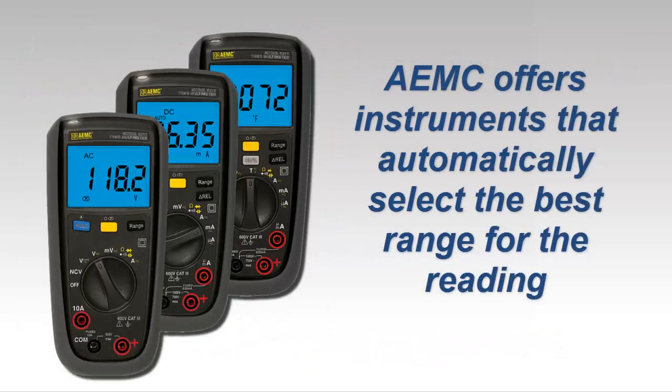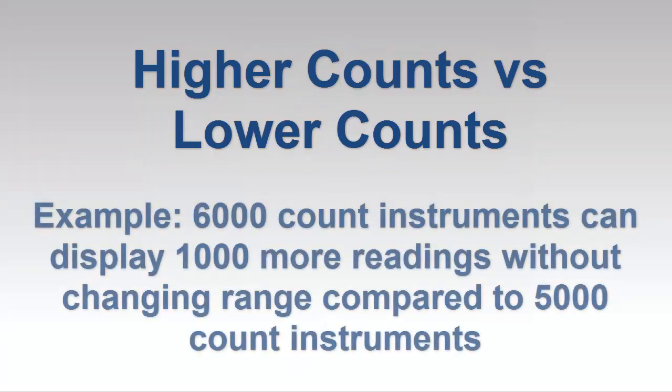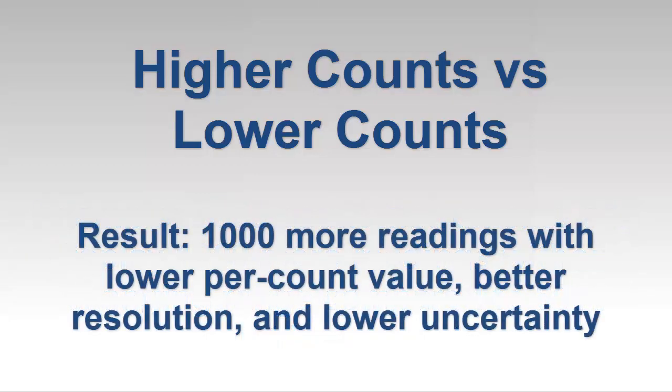AEMC features instruments, including multimeters, that perform auto-ranging for automatically selecting the most appropriate range for the reading. This also illustrates the advantage of higher count instruments. For example, a 6,000-count multimeter can display 1,000 more readings than a 5,000-count model without changing to the next higher range. Since these 1,000 additional readings will have a lower per-count unit value, they will result in a lower uncertainty.